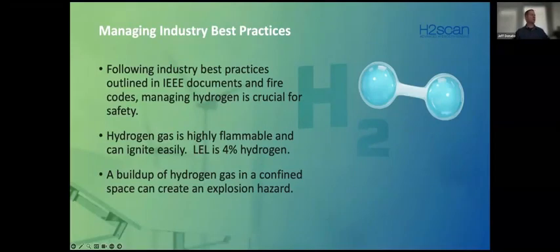Yep. Okay, great. So really, there's a couple things that I want to point out when we talk about managing hydrogen. We have industry best practices that we're trying to follow, such as IEEE documents. We also have codes as well. In all flammable gases, hydrogen follows the same suit when it comes to making sure that we maintain a safe level below the lower explosion limit. Hydrogen is explosive at 4%, and the code basically states that we have to stay within 25% of the LEL.